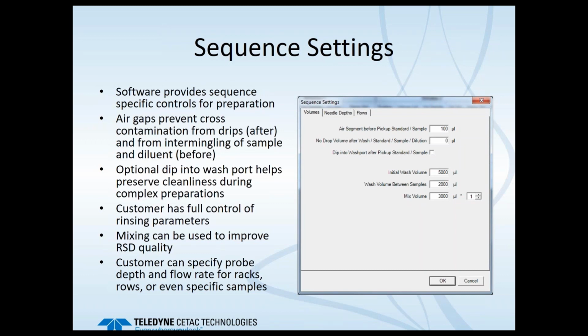Some of the sequence settings are listed here. It's very flexible. So I mentioned there's an air segment option that prevents cross-contamination. There's also a no drop volume, which is to avoid any sort of drips. And then you can have it dip into the wash port, but it's all very customizable. The rinse is totally up to the user, and that can be removed entirely for things like dispensing. If you don't want it to go back to the rinse station, there's no requirement to. And there's also the option of mixing. So you select the volume you'd like to have it mixed and how many iterations. Essentially, it goes into the prepped sample, pulls up an aliquot and redispenses it, which is a fairly rudimentary mixing, but it can be very effective.